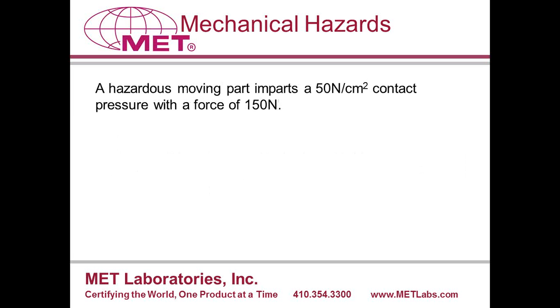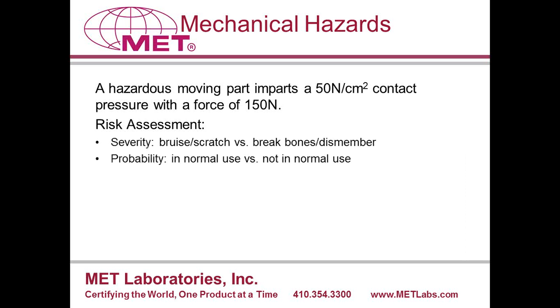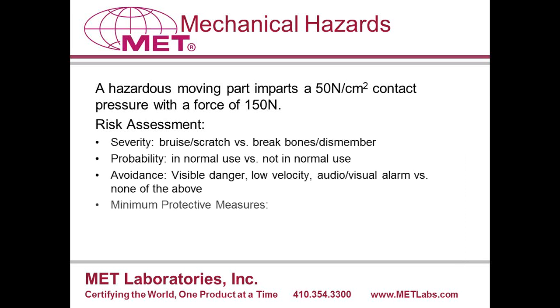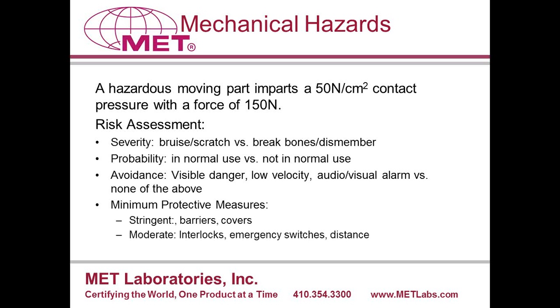Now, hazardous moving parts are defined as parts which impart a 50 Newton per centimeter square contact pressure with a force of at least 150 newtons. Whenever you have hazardous moving parts, if you have not sufficiently removed all the hazards, you need to do a risk assessment to demonstrate that the hazard has been reduced as far as possible. You want to judge the hazard in terms of severity, probability, and ease of avoidance. Then you will look at all the possible means to eliminate and reduce the hazards, starting with stringent means such as barriers and enclosures, moderate means such as interlocks and emergency switches, or if the hazard is not severe, simple markings, audio-visual signals, or instructions.